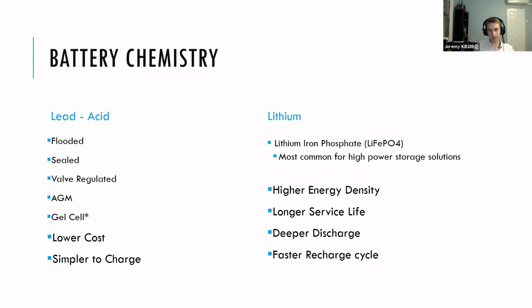These have major advantages over lead acid batteries in energy density, kind of leading the way with those. Meaning you can get a lot more power out of a smaller, lighter battery, which again may or may not be an advantage depending on your application. Something that is fixed, while you may have a smaller footprint, which may be an advantage, the lighter weight may not get you as much. But there are also some advantages in the service life, your ability to discharge them to a much lower voltage and to cycle them back up to full charge faster.